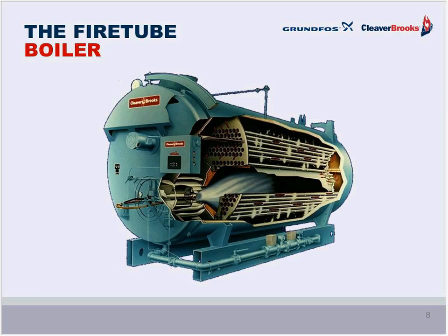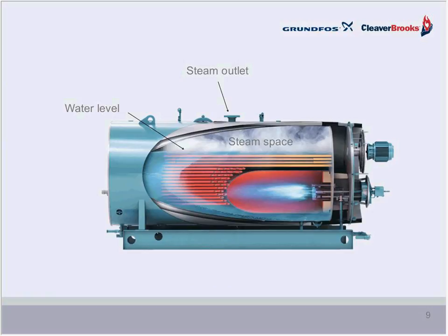And then we have the fire tube boiler. And as noted last month, different from the water tube boiler, in that the flame and the hot gases are in the tubes and the water surrounds them, as you can see in this picture. But what is important for today's discussion is again noting the critical water level that we need to maintain and the steam space, that area along or just below the outlet connection, which then leads to the steam system, the piping.